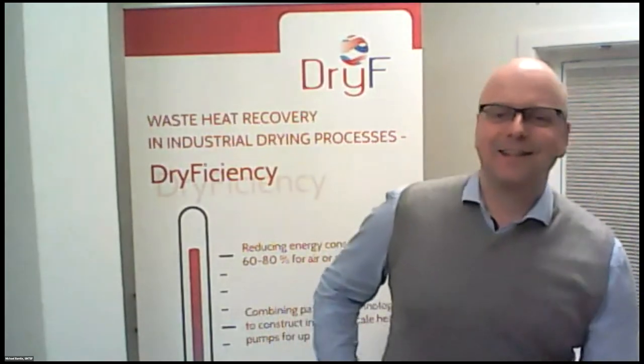I think the open loop takes around 45 minutes to maybe 1 hour to come from a very cold state up to the operational temperature where we want to have it. So this 1 hour is not efficient at all. That's like a COP of around one, it's direct heating. But above that, it's then much better. So of course we want to avoid total shutdown and starting up again from lower temperature. However, it also takes time for the heat pump to cool down. Once you had it at the operational temperature, you can shut it down for 30, 40 minutes and it doesn't cool down. There is a certain thermal inertia in the whole system.